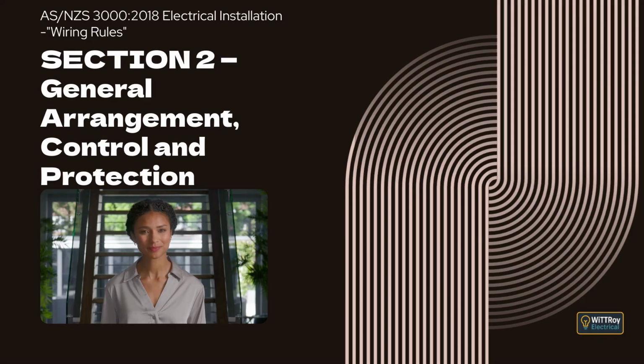AS/NZS 3000 Section 2.6, New Zealand clauses only, additional protection by RCDs. Clause 2.6.1, General. This clause explains why RCDs with a rated residual operating current not more than 30 mA are used as an extra layer of protection. They give added safety in places where earth leakage current might become dangerous, or where people might use equipment carelessly. These RCDs help reduce the risk of electric shock, but they do not replace the main protection required by Clause 2.4. They do not protect against faults between live conductors. They also do not protect against dangerous voltages that may come into the installation from the supply neutral.